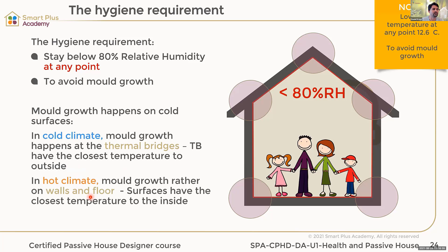In a hot climate, mold grows on the walls and floors — surfaces that have the closest temperature to the inside. When we cool it down, the relative humidity goes up in the building, the surfaces get colder, and we have condensation issues on walls and floors. So in hot climate, it's rather walls and floors; in cold climate, it's rather the thermal bridges.